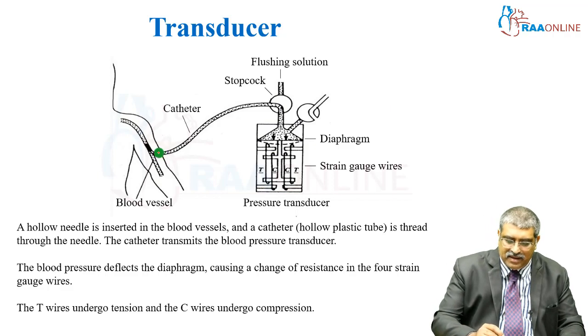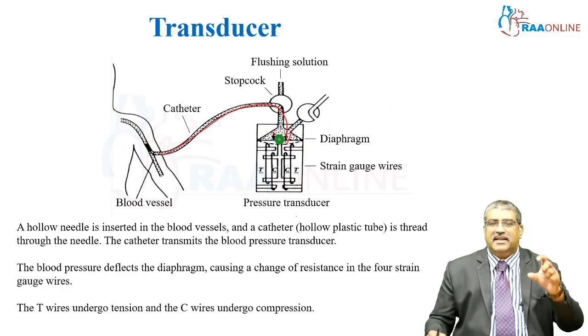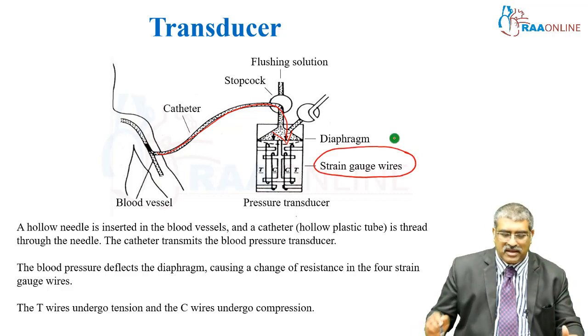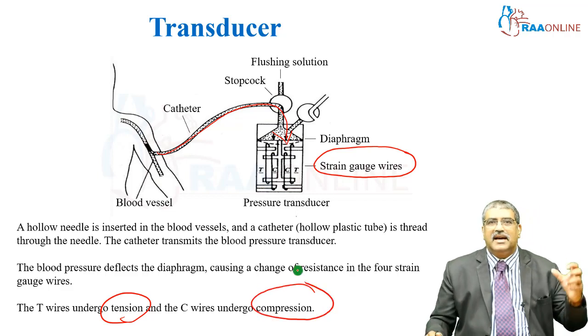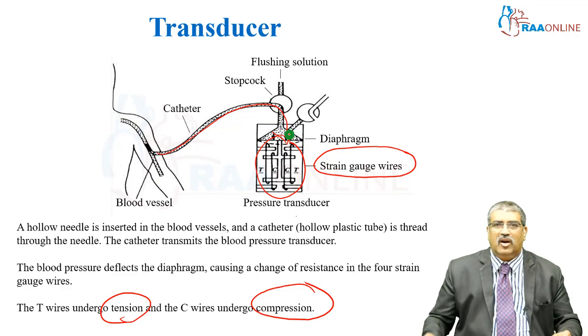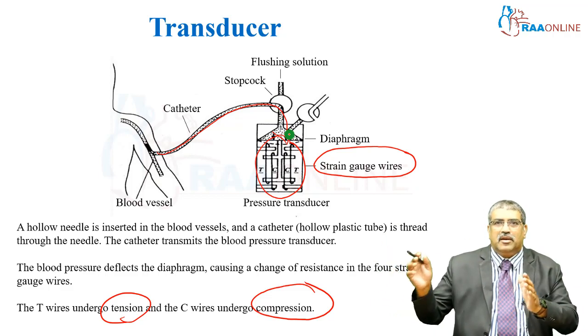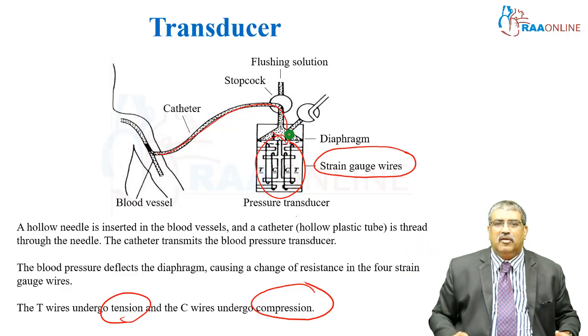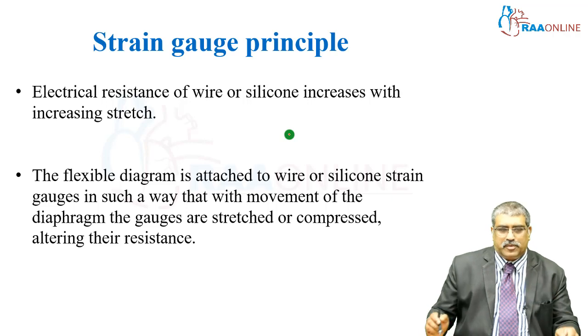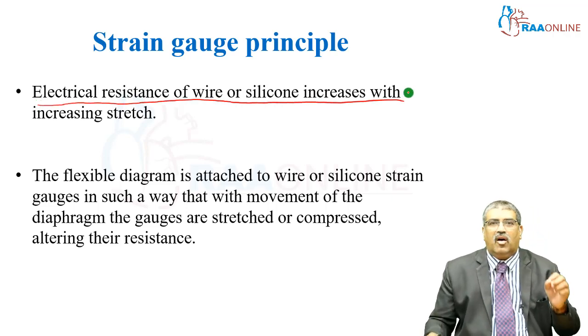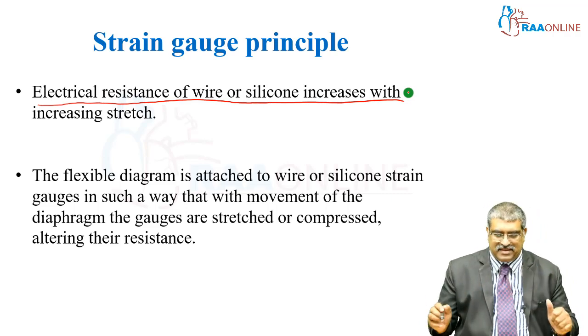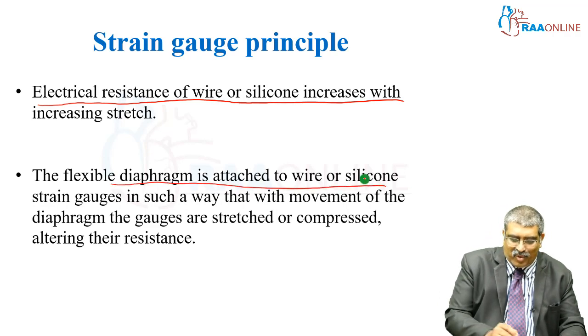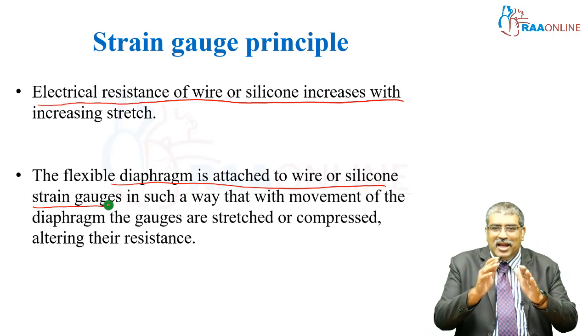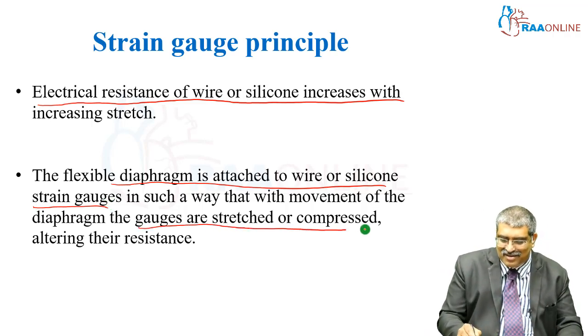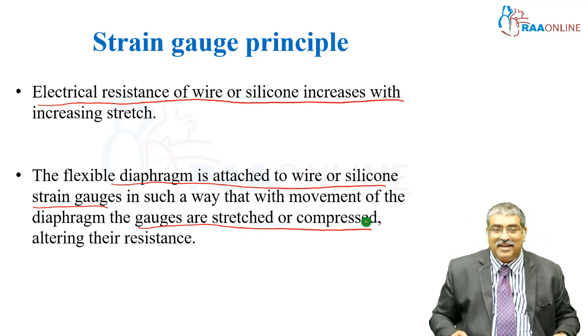In other words, the pressure is exerted on the diaphragm and there are 4 strain gauge wires, 2T and 2C, that is tension wires and compression wires. As the pressure is exerted on the diaphragm, the resistance gets altered, and this through the Wheatstone bridge is reflected back on the microprocessor. From there, it goes into a digital format. To summarize the strain gauge principle, electrical resistance of wire or silicon increases with increasing stretch. The flexible diaphragm is attached to the wire or silicon strain gauges in such a way that with any movement of the diaphragm, the gauges are stretched or compressed, altering the resistance.